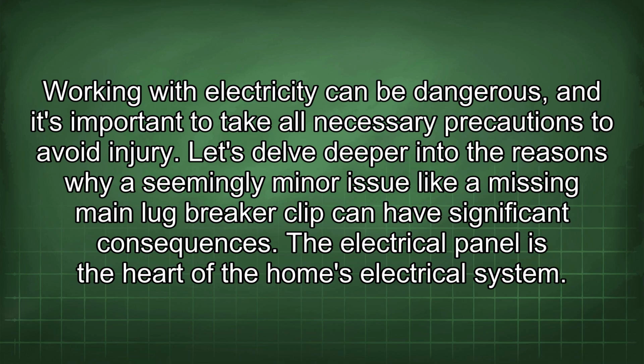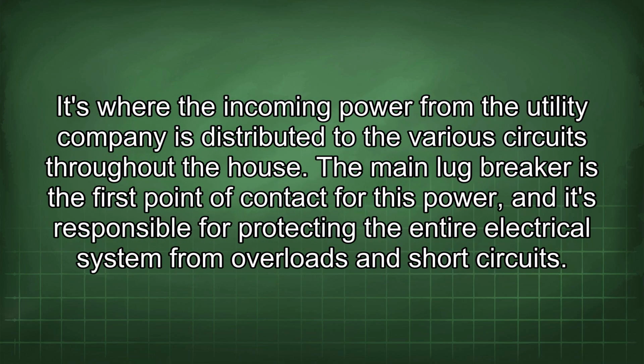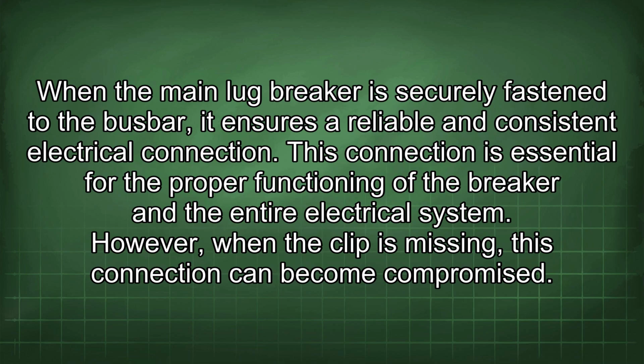Let's delve deeper into the reasons why a seemingly minor issue like a missing main lug breaker clip can have significant consequences. The electrical panel is the heart of the home's electrical system. It's where the incoming power from the utility company is distributed to the various circuits throughout the house. The main lug breaker is the first point of contact for this power, and is responsible for protecting the entire electrical system from overloads and short circuits. When the main lug breaker is securely fastened to the bus bar, it ensures a reliable and consistent electrical connection. This connection is essential for the proper functioning of the breaker and the entire electrical system.